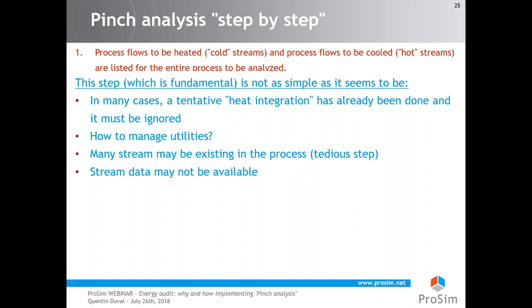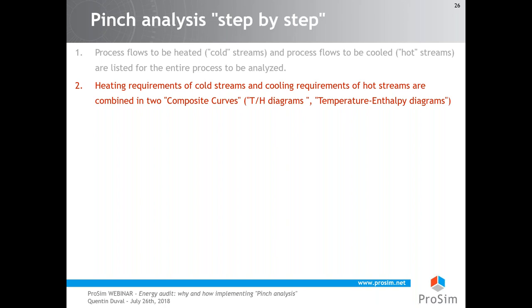Another important consideration is the number of streams and the fact that the process may run in batch sessions. In this case, streams are not continuously available and must be handled accordingly. Missing data and a relatively high number of streams make the method more tedious. Nevertheless, this data collection is the most important part of the pinch method to get good results — the more accurate the data, the more relevant the energy integration. After data collection, we obtain a list of cold and hot streams.